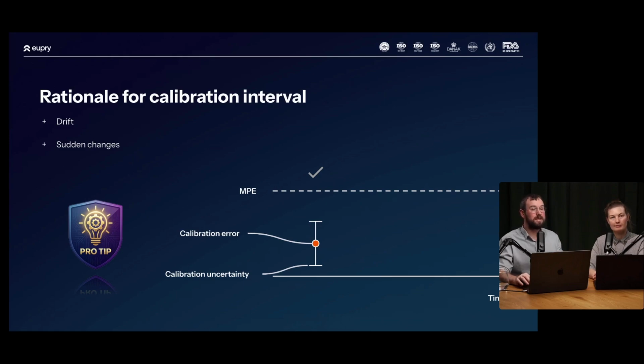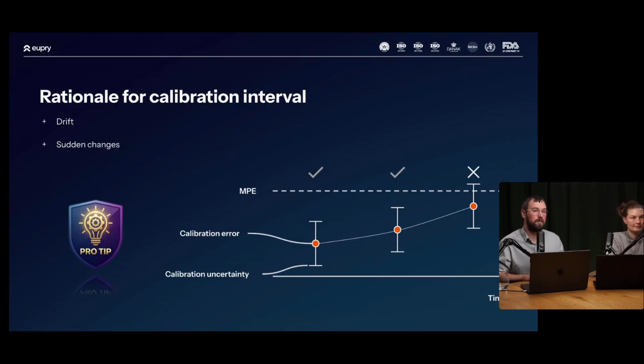So let's say this is an example of first year's calibration. Everything is fine. We're within our MPE. Second year, everything is fine, or however interval you like to choose. But at the last point, it's going to go outside. And this is the tendency we're trying to predict. And the change from year to year, which is often drift, is what sets our calibration interval.